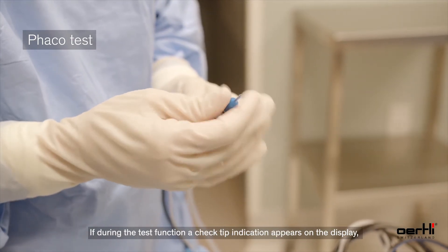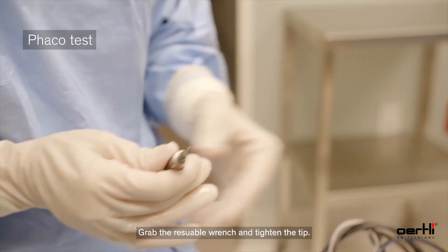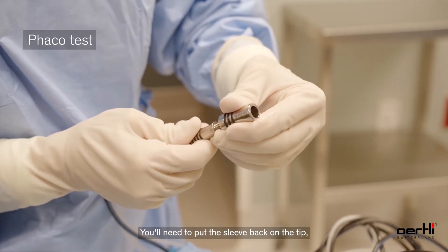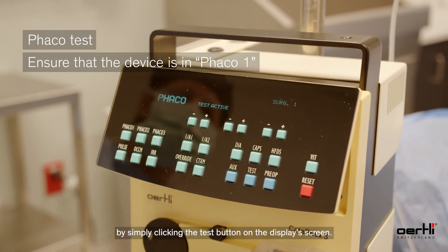If during the test function a 'check tip' indication appears on the display, simply remove the sleeve, grab the reusable wrench, and tighten the tip. After this process is done, put the sleeve back on the tip, reattach the test chamber, and go through the Phaco test process again by clicking the test button on the display screen.